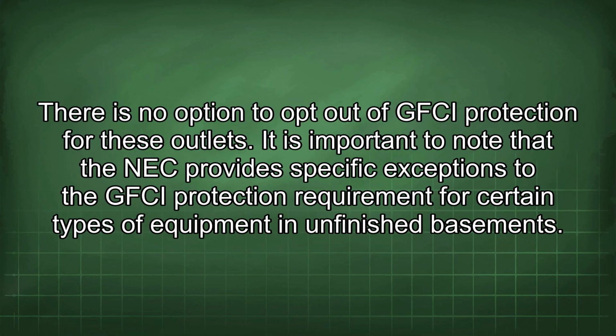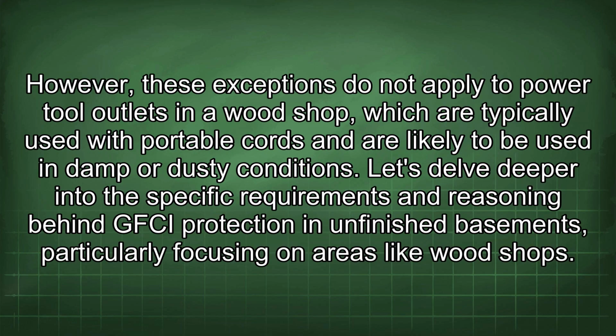There is no option to opt out of GFCI protection for these outlets. It is important to note that the NEC provides specific exceptions to the GFCI protection requirement for certain types of equipment in unfinished basements. However, these exceptions do not apply to power tool outlets in a wood shop, which are typically used with portable cords and are likely to be used in damp or dusty conditions.